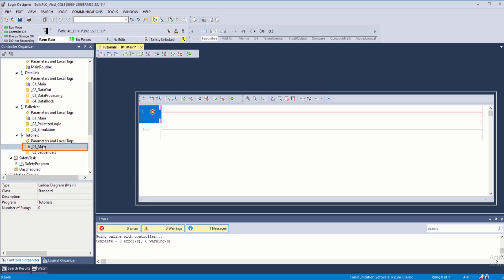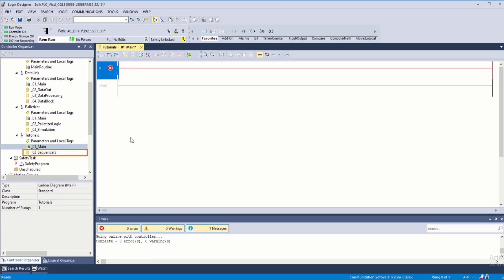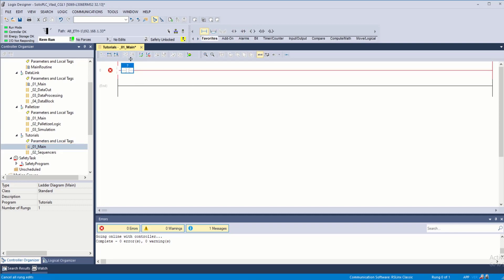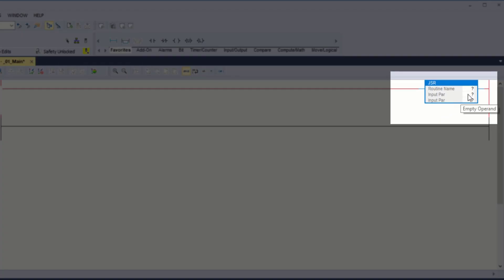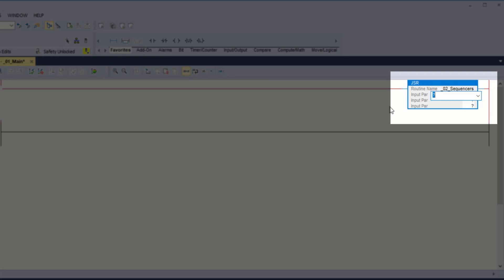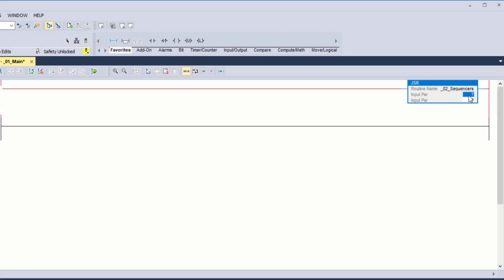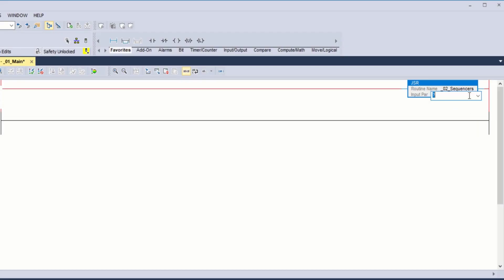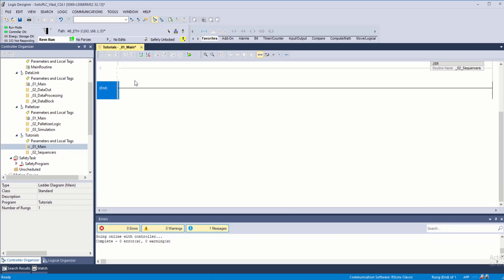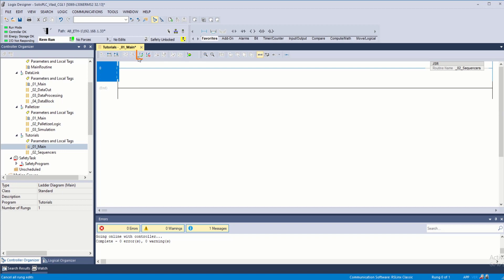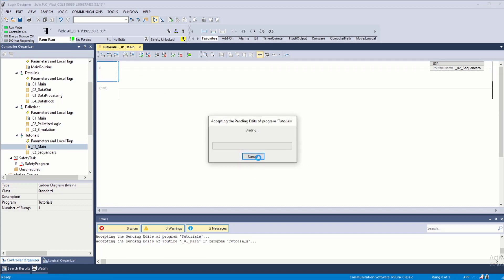Under main sequencers, press OK. Now we need to add a jump subroutine from our main in order to execute the sequencers. I'm going to double-click main and then add an instruction — I double-click and change that to a JSR or jump to subroutine. Here I indicate the name, underscore zero two, press enter once it auto-completes. That should be all we need on the main side. Select the rung, accept all changes, and press yes.